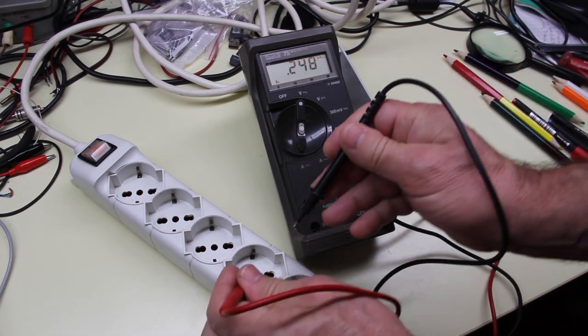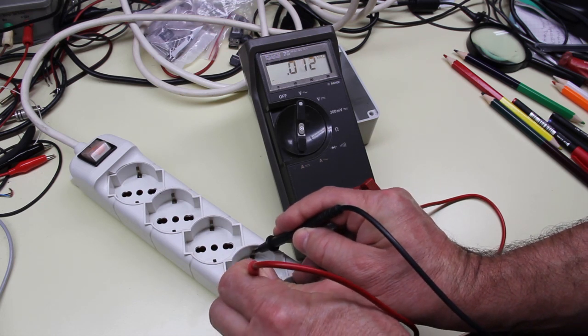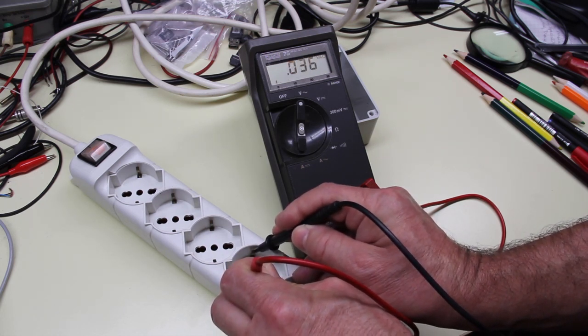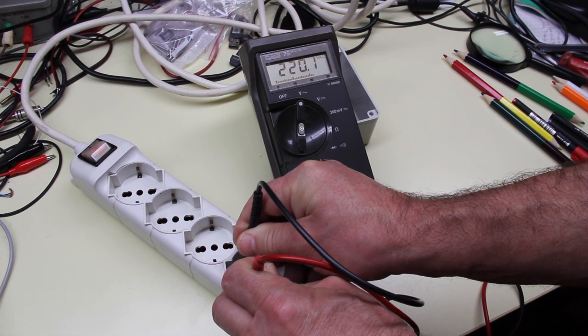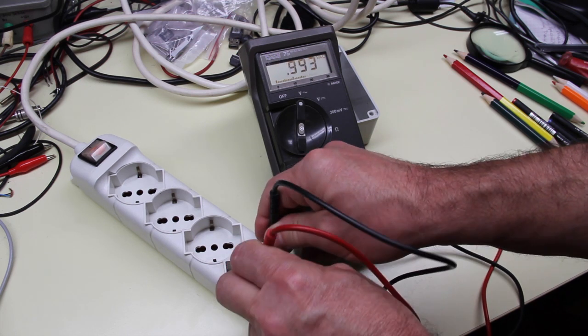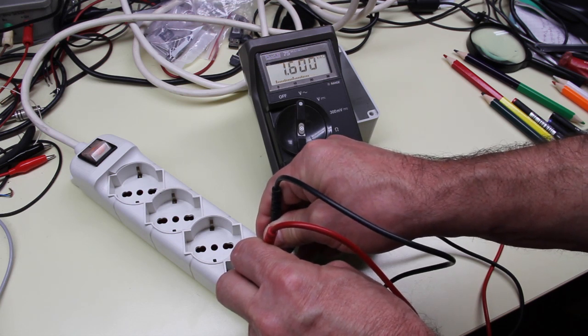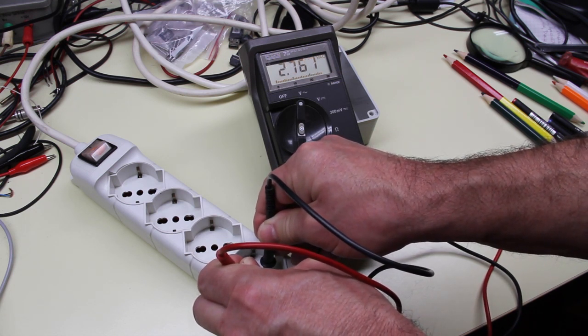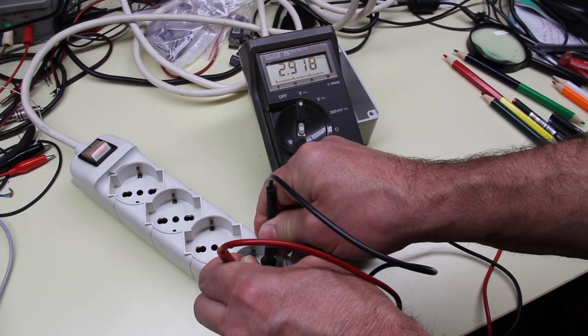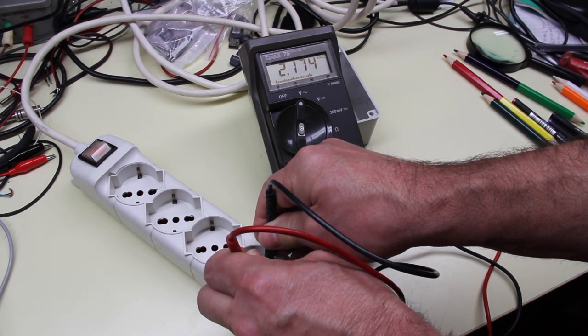And I can demonstrate this by reading with the multimeter. This is the same earth - zero volts. This is the earth toward the live - 220 volts. Earth and neutral, and we have 2.6, 2.7 volts, 2.8, 2.9 - it is not stable, it is variable, but definitely not the same voltage.